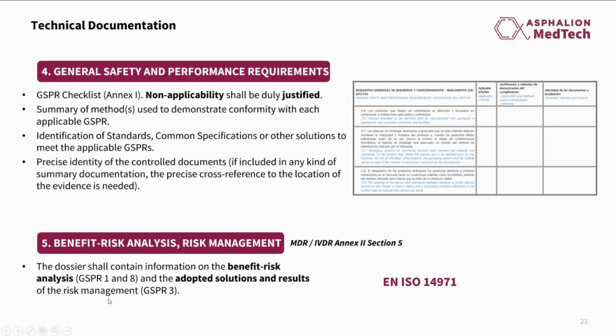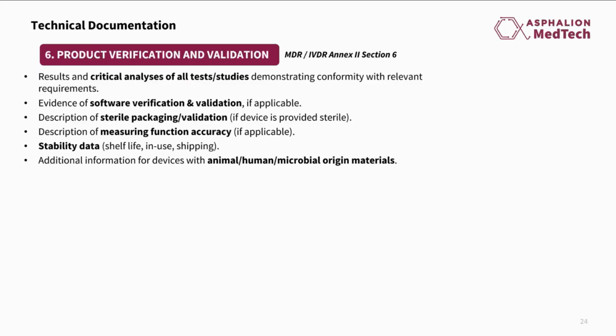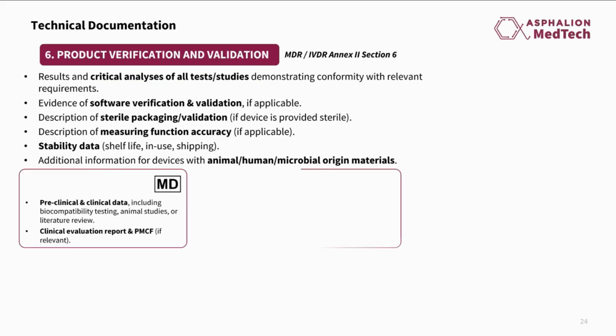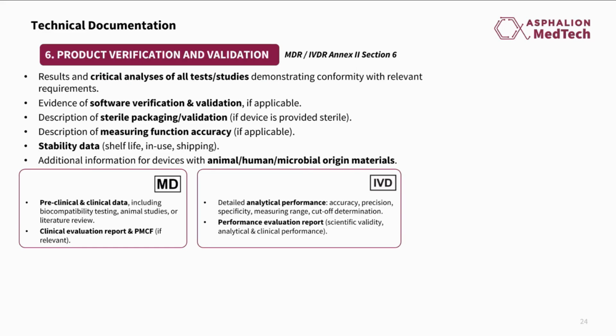Another key module of the technical documentation is the benefit-risk analysis and the risk management. Here you need to include all the risk management activities for assessing the risk that could come from the whole life cycle of your device, and how you have constructed control measures to reduce all these risks as far as possible. Here, the relevant standard is ISO 14971. And finally, one of the final modules is regarding product verification and validation. In this module is where all the preclinical and clinical evidence shall be discussed, and also how your device has shown that, in a real-world scenario, it is able to demonstrate compliance with the safety and performance requirements.